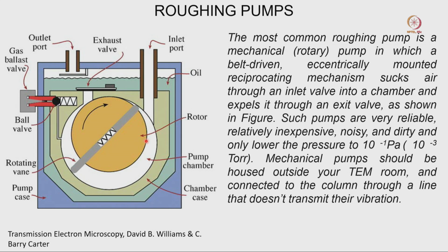You can see this entire chamber will be opened up somewhere here, and whatever air, moisture or remaining pressure comes here will pressurize this exhaust valve, and the exhaust valve will open up, which helps us remove that moisture. This rod rotates constantly in this direction, trying to remove the excess moisture or air.